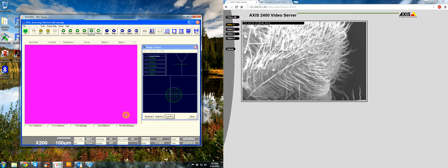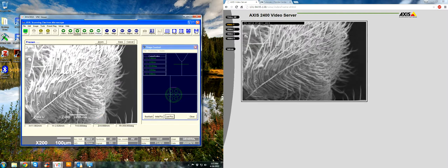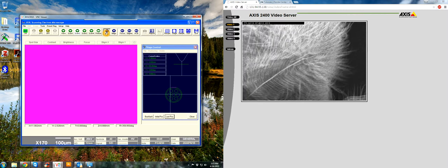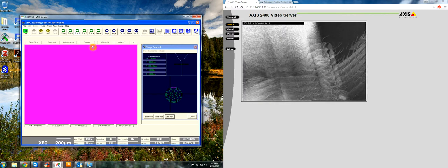Okay, the scan 4 is almost complete. Okay, and here's scan 4. It's a really nice image. You do this, you save it this exact same way: File, Save Image. And these are the basic operations for the SEM and acquiring an image. If you want to go back to navigating, you just hit scan 2. You can zoom out and explore your sample.